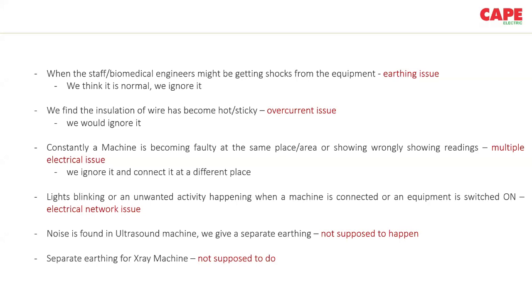The next thing is that we might have noticed some constant failure of an equipment at a particular place or a particular area. Or particular equipment may be showing some wrong readings in a particular area. Why that happens is that it might be due to multiple electrical issues. Sometimes we'll ignore it because when we connect it to a different place, it'll work properly. We should not ignore that previously that machine has shown some wrong values or it was not working properly. We have to check the machine as well as the electrical connections there.